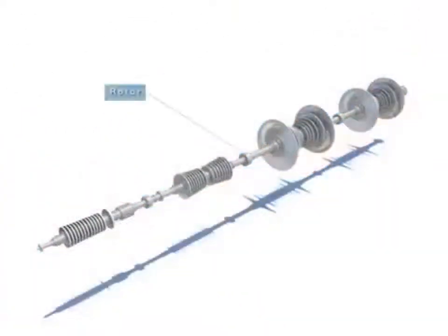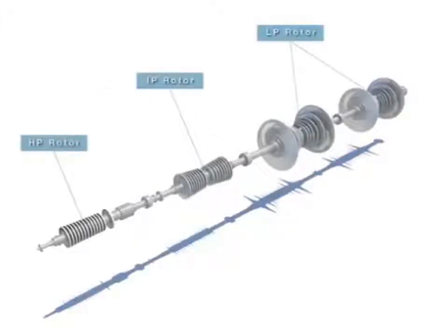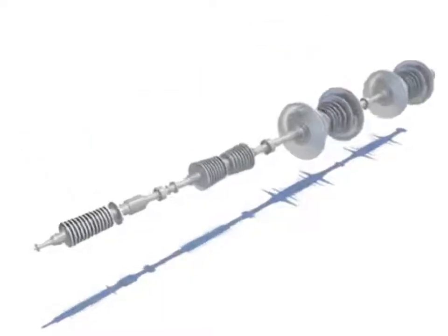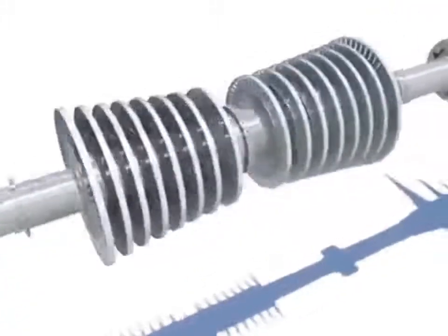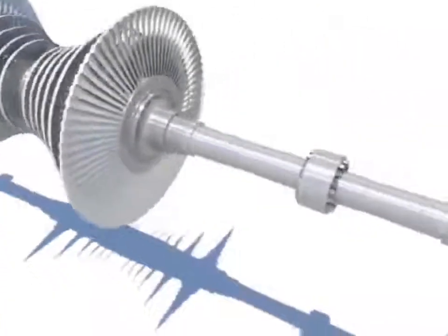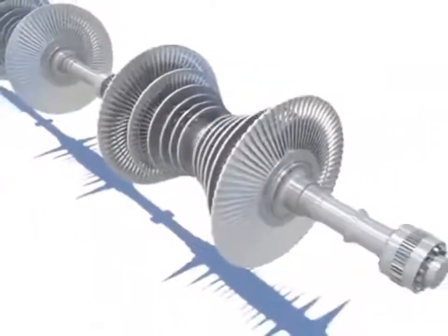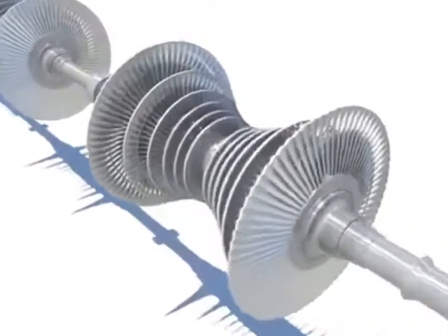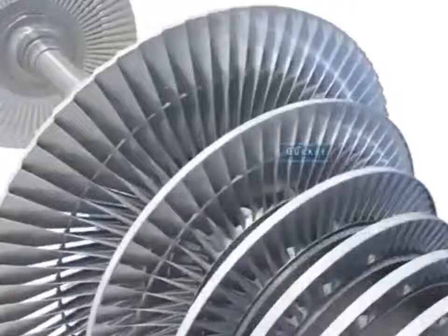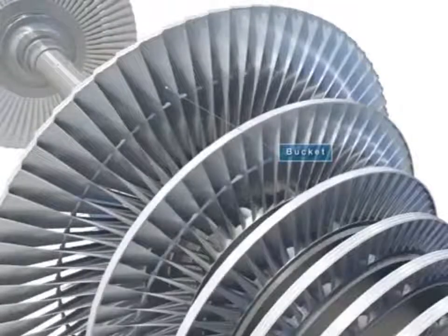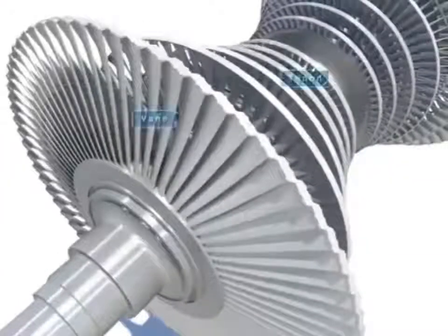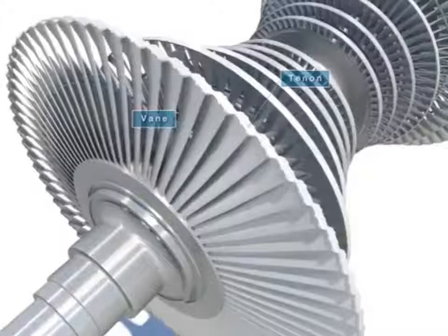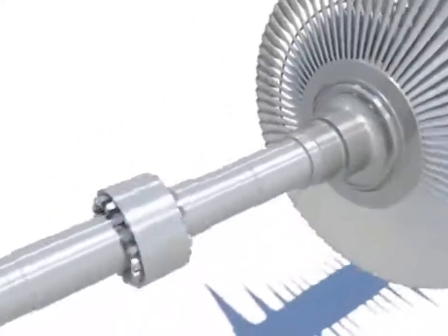The rotor consists of a row of wheels, which is a body with shaft, and is designed to stand the centrifugal load of the impulse bucket connected to the wheel mechanically. The rotor works for changing circumferential power of the rotative blade into turning power through the wheel. The bucket is assembled to the turbine wheel part and works for changing heat energy from the steam into turning motion by conveying it to the shaft. Also, it changes the fluid flow by using the entrance and exit angle of the bucket.